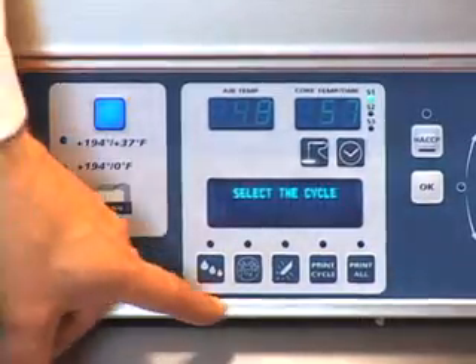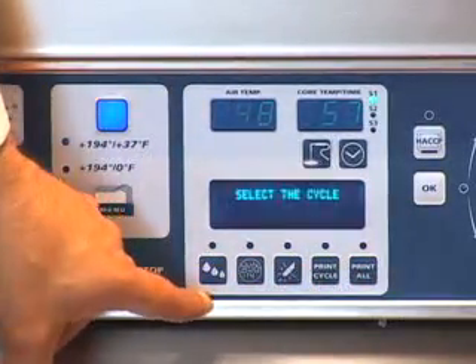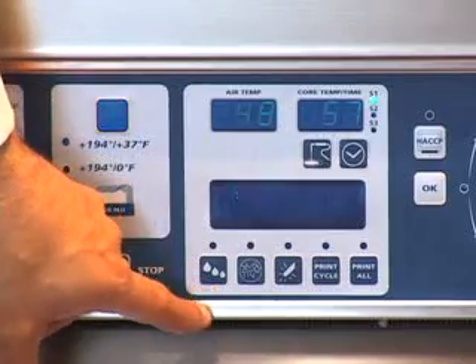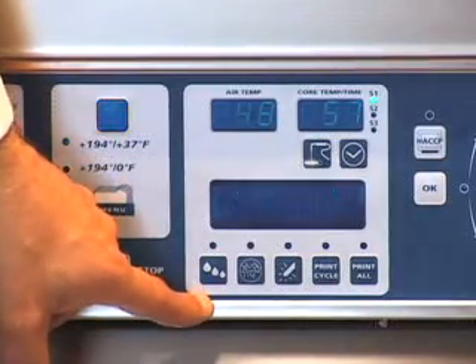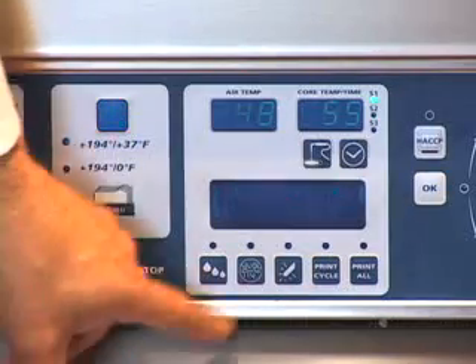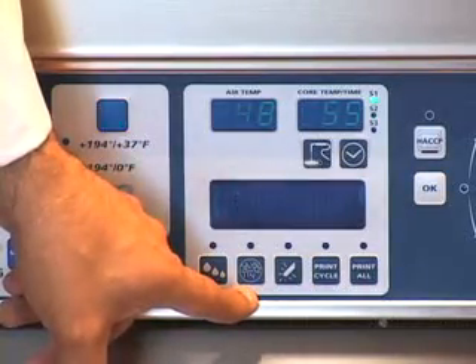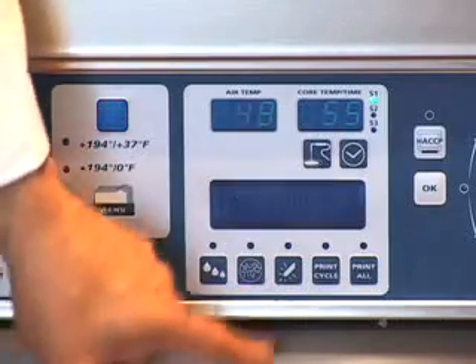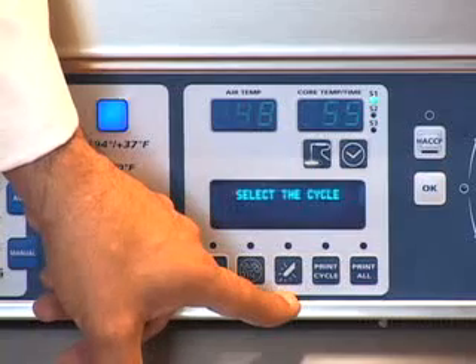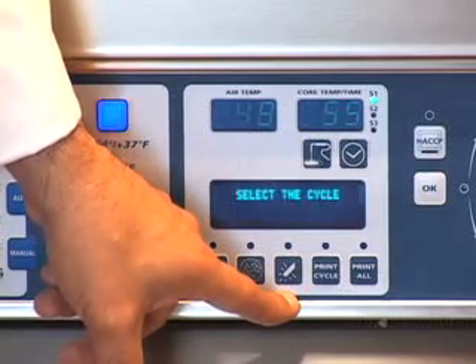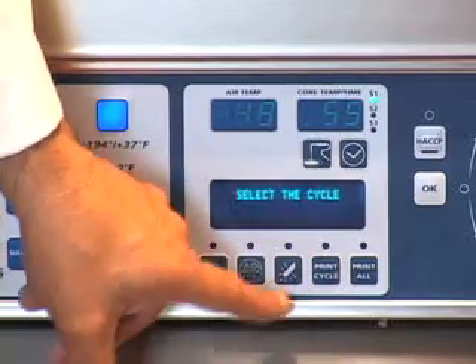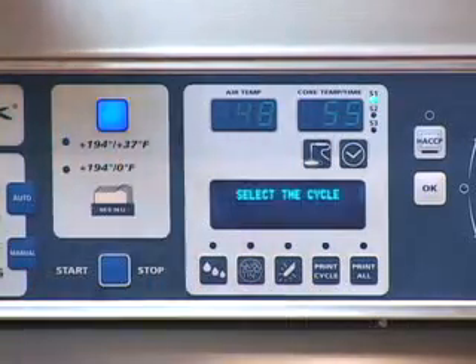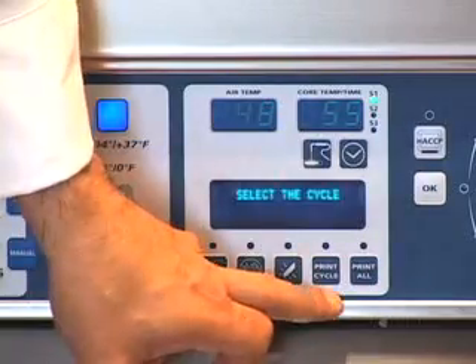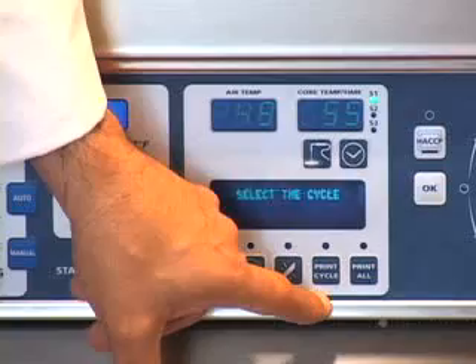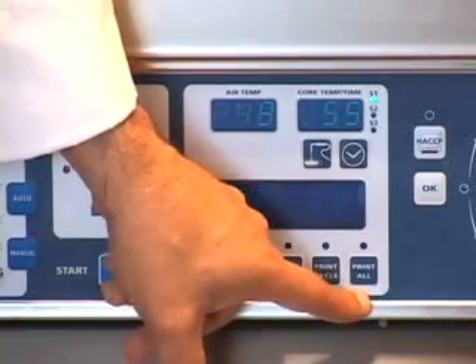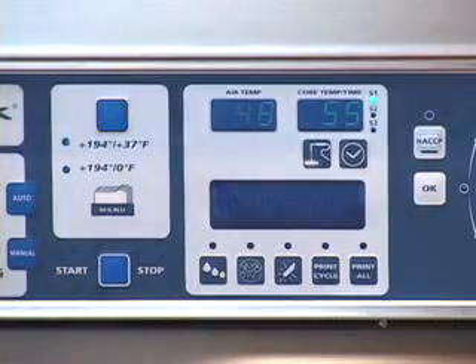I'm now going to explain what the 5 buttons on the bottom of the display are for. The first button, which has 3 water drops on it, is for defrost. This is a manual defrost unit, and you have to defrost the unit when you're done chilling or shock freezing. The second button here is for the UV sterilization system, if your unit is so equipped. The third button is probe heat. When the probe is inserted into a product that has been shock frozen and it's a delicate product, you can use this button. It'll heat the probe for 5 seconds to make the probe easily removable from the product without damaging it. The last 2 buttons are for either printing your last completed cycle, or for printing all of the cycles that are in memory using the optional handheld printer.